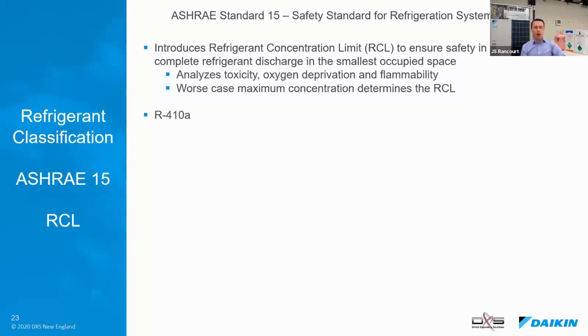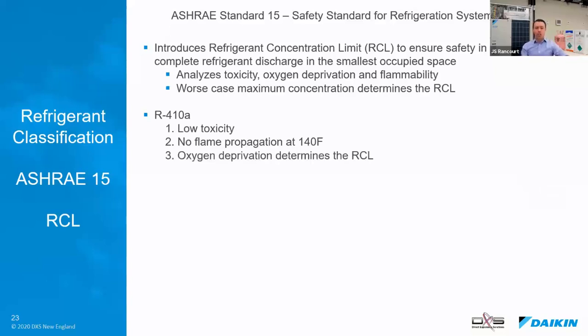So let's go pick on R410A over here a little bit. I have not introduced R410A yet. I will in a minute. But in terms of ASHRAE 15, R410A for all three categories is low toxicity. It has no flame propagation at 140 degrees. So the oxygen deprivation determines the RCL. And most engineers know this. And there's the famous limit of 26 pounds per 1,000 cubic feet that you need to abide by.